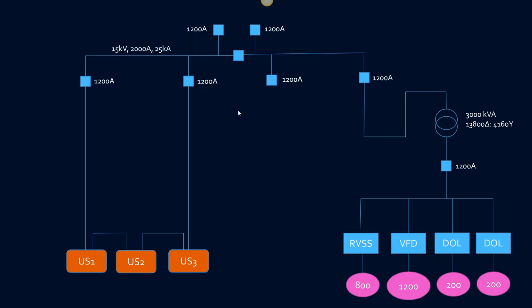Let's see if I have a pointer here. You can see over here we have a transformer, and then a lineup with a main breaker that feeds some medium voltage motor control. So perhaps we have some medium voltage chillers or medium voltage pumps. We have one 1200 horsepower, one 800, and two that are 200 horsepower. And based on input from our client, the 200s are fed from direct across the line contactors. The 800 is fed with a reduced voltage starter, and the 1200 is fed with a medium voltage VFD.